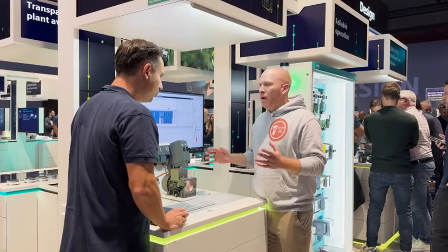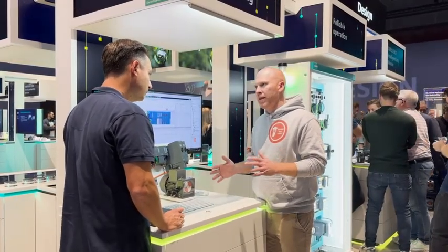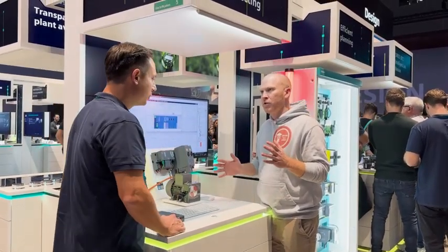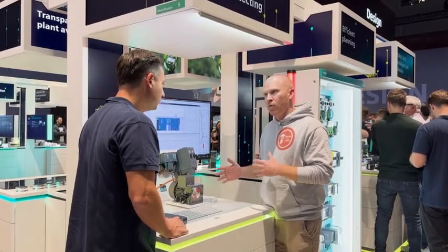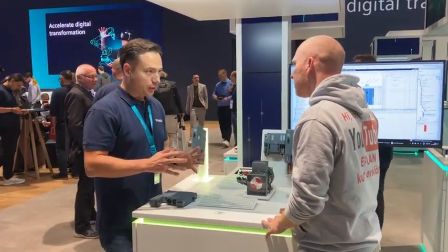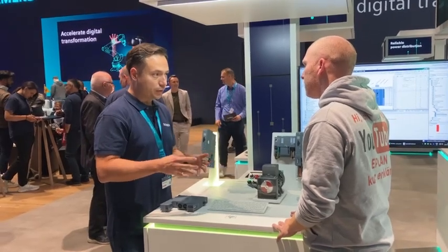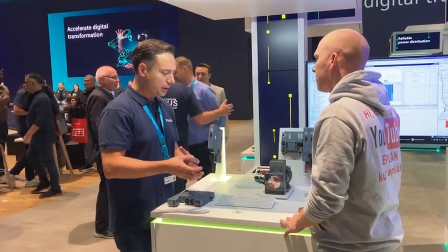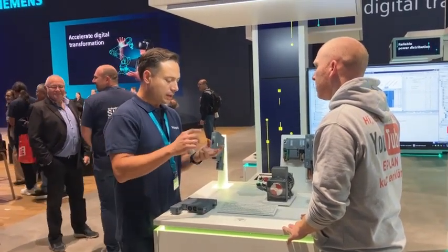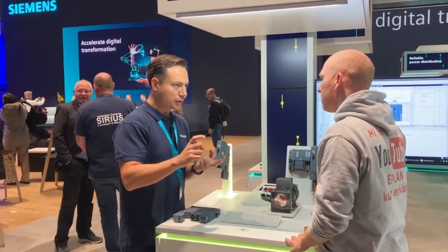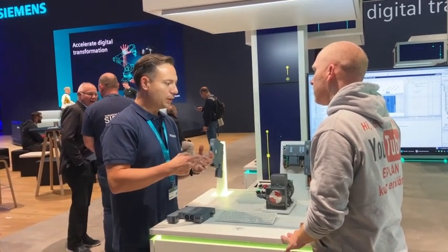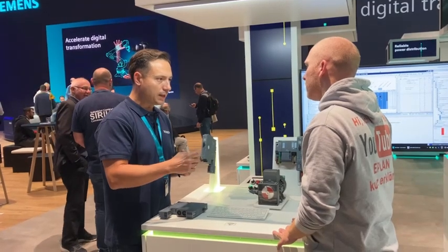Yeah. Let's talk about another topic. Nowadays we have high efficiency motors, and this could sometimes be a problem for a normal MCCB, right? Yes. Because of the big inrush current. That's correct. With a full electronic starter, you have some solution for this? Yeah, that's correct. With the e-starters we have brought, we want to also address this challenge. We know many customers are forced to upgrade to high efficiency motors, and these high efficiency motors bring up the challenge of inrush currents and high starting currents. And directly proportional to the current, we have also the torque. So the challenge is these inrush currents could lead to trips of the protective devices that are upstream.